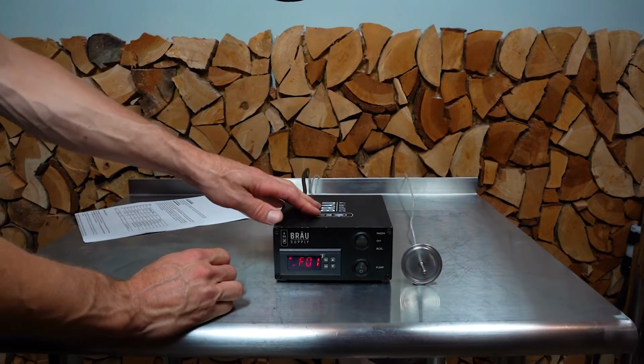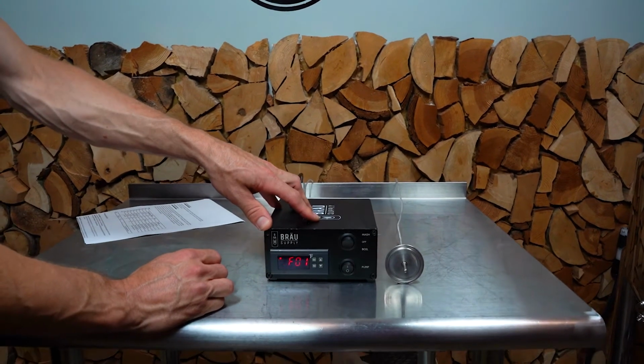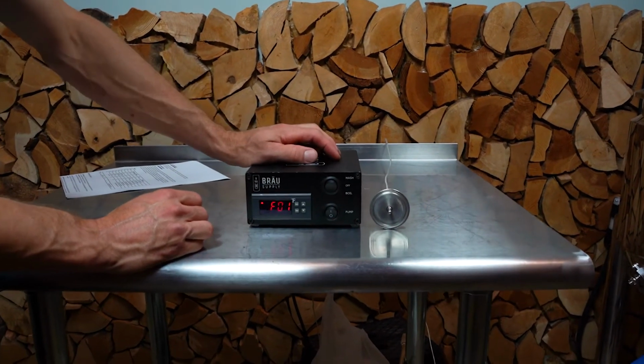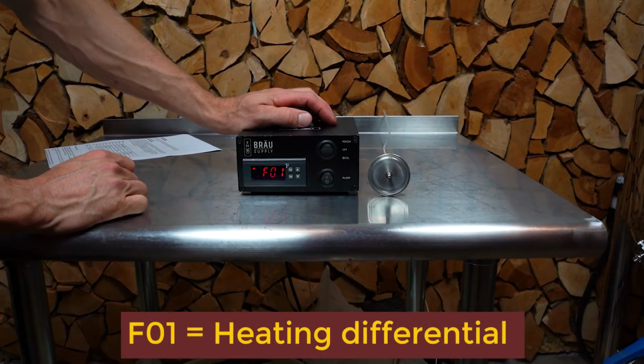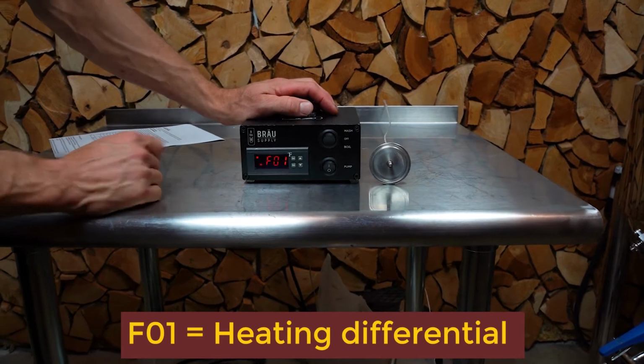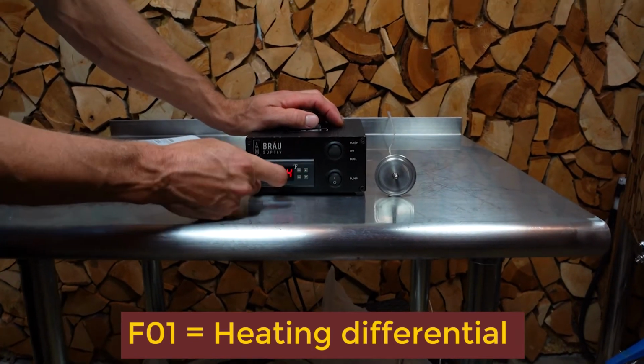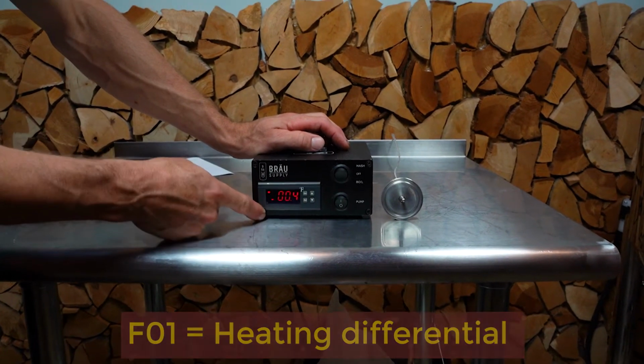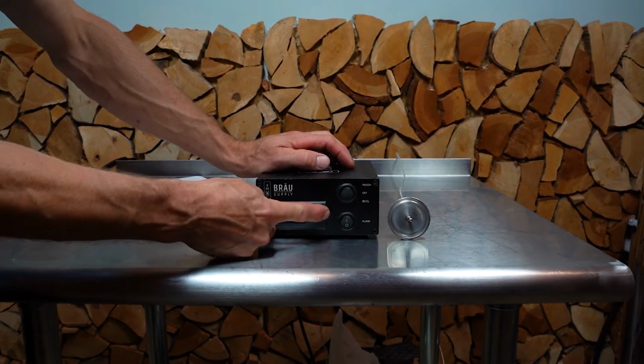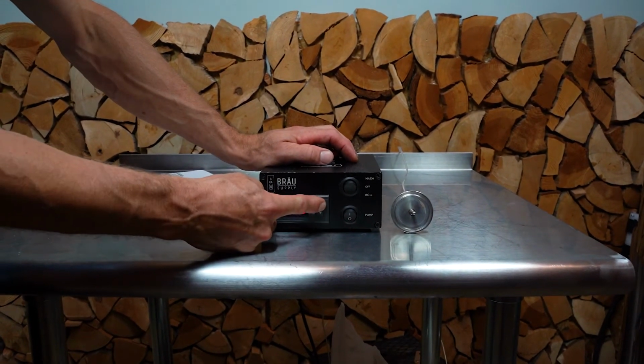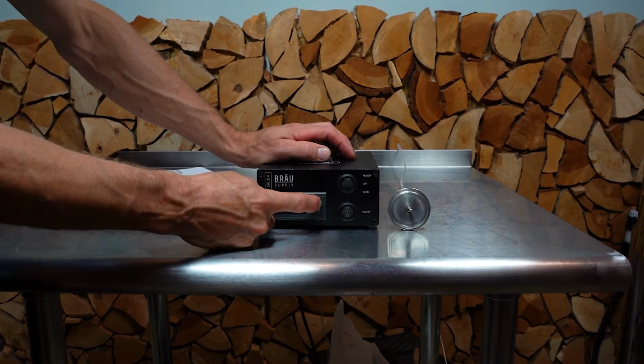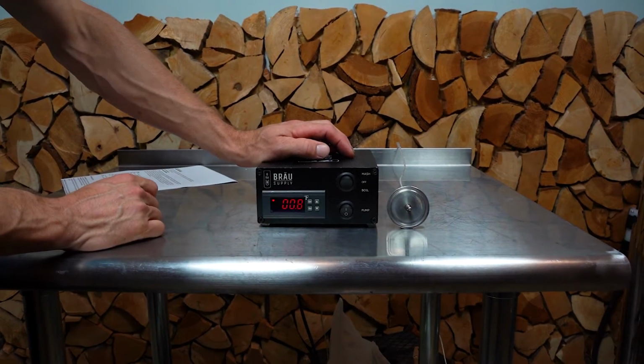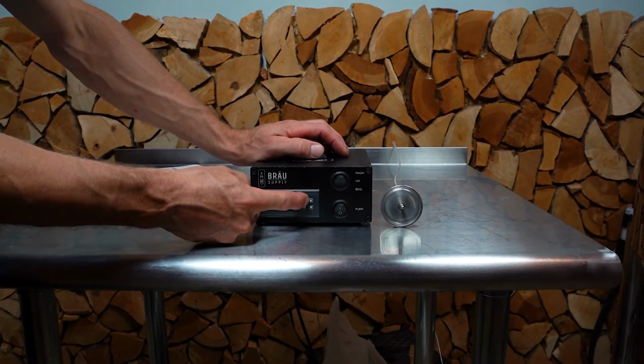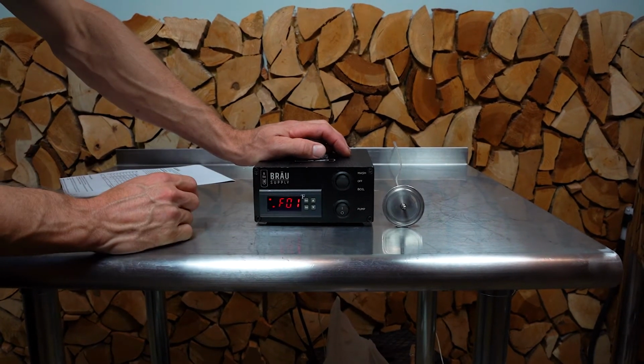Now we'll go to F01, and that's the up arrow. And F01 is a heating differential. So this is how accurate you want to maintain, for example, your mash temperature. Press set, and I've got it set to 0.4 degrees. It might be a little bit tight there. Maybe you're best off at around 0.8 degrees or 1 degree for heating differential. Press set again, and it brings you out.